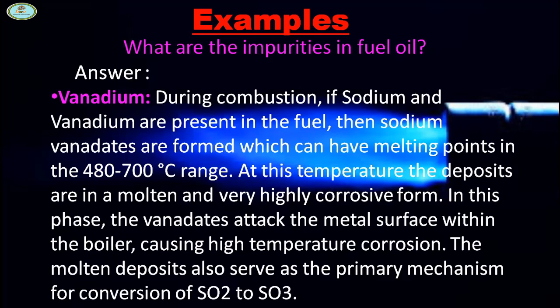Vanadium: during combustion, if sodium and vanadium are present in the fuel, then sodium vanadates are formed which have a melting point in the 480 to 700 degrees Celsius range. At this temperature, the deposits are in molten and very highly corrosive form.